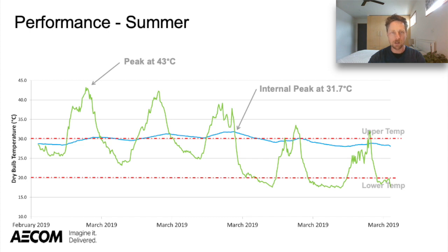We had external temperatures up to 43 degrees for a number of days, both before the BMS started recording data and again once the building was occupied. Even after these consecutive hot days, the internal temperature peaked at around 32 degrees, consistent with how we expected the building to perform, which was great news for the building and its occupants.